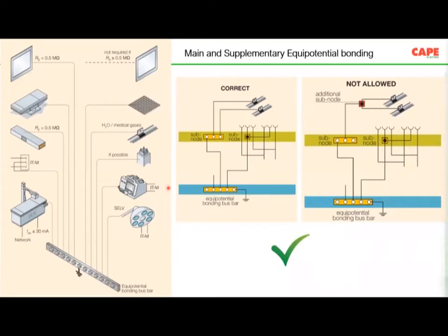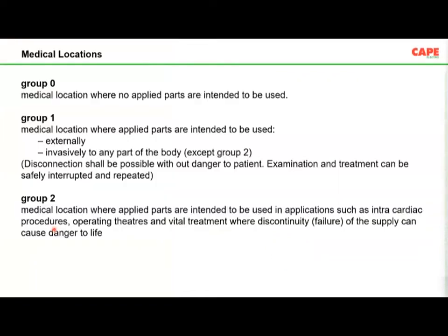Please don't follow the medical equipment vendors' claim for having separate earth electrodes. Separate earth electrodes are wrong. This separate earthing, if they claim, is something like from their equipment to the supplementary equipotential bonding, you need a separate wire. So this is much more efficient, and of course it is very much cost saving, very much economical. So this is what is recommended in this standard.